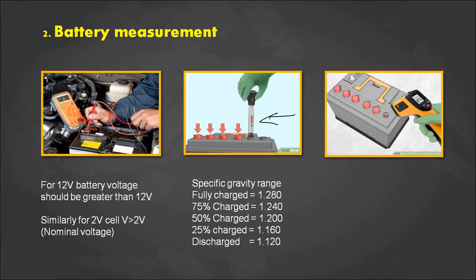Similarly, we have to check the temperature of a battery. This temperature should be near the room temperature. If the temperature is greater than the room temperature, we have to inspect the battery in order to avoid any exothermic reaction inside the battery. Thereby we can avoid the explosion of the batteries. So these are the battery measurement parameters we have to measure, and we have to maintain a record of these three parameters.